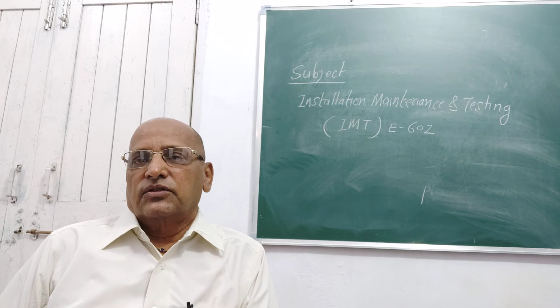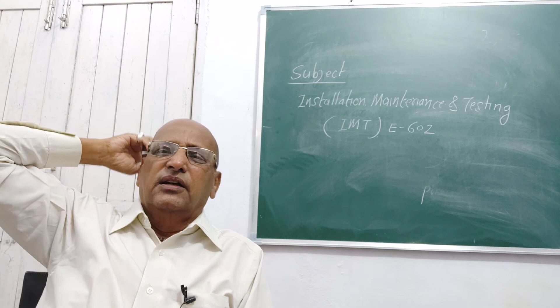So that should be done first. After grouting the RS joist in the ground, you first install the double C channel for putting the transformer, and when you put the transformer on the double C channel and it is properly tightened with the help of nut bolts and clamps, after that the other equipment like the DO fuse, above that DO fuse the lightning arresters, and above the lightning arrestor the AB switch. These are also termed heavy equipment, because their weight varies from 100 kg to 200 kg.